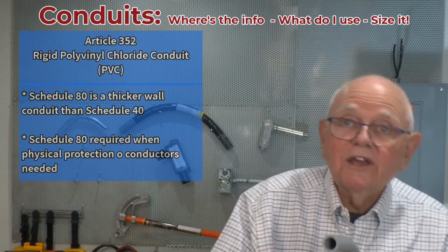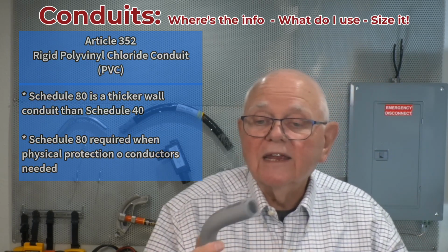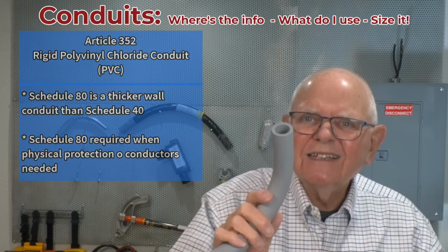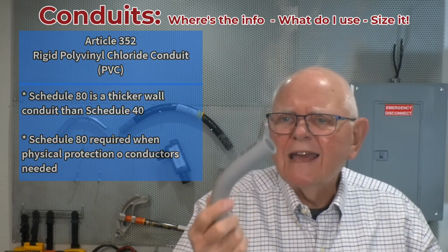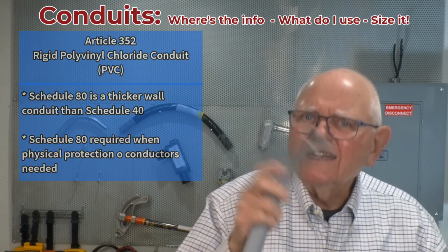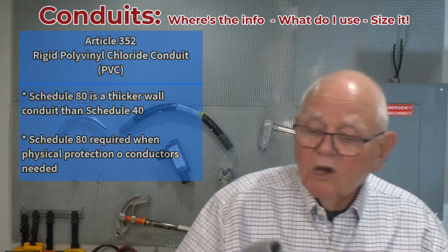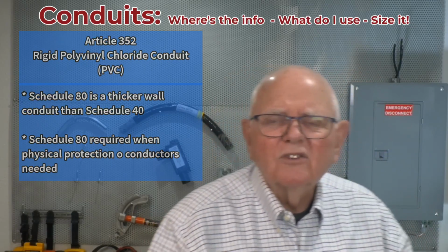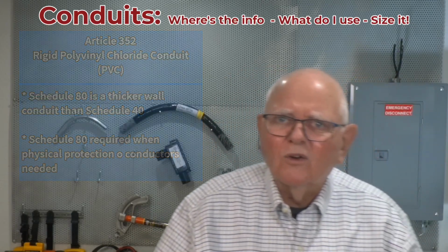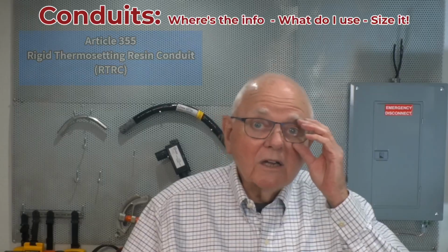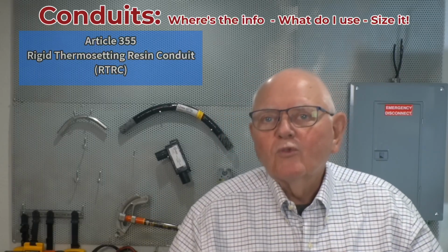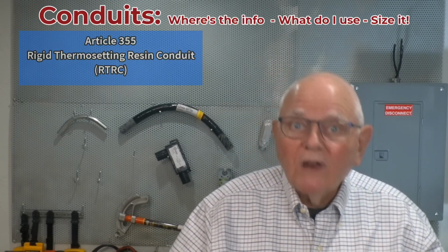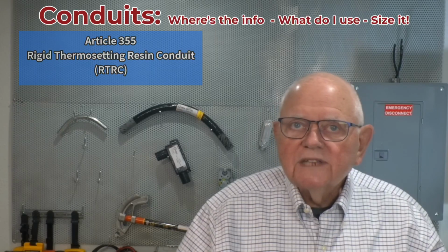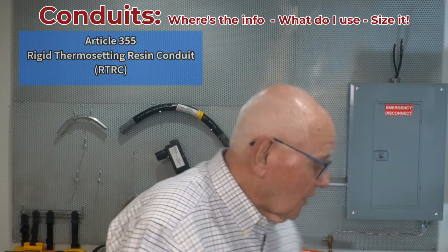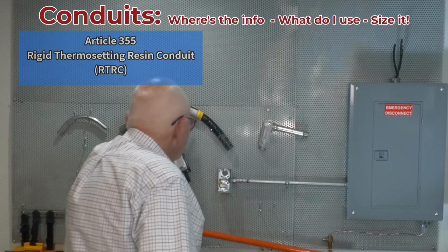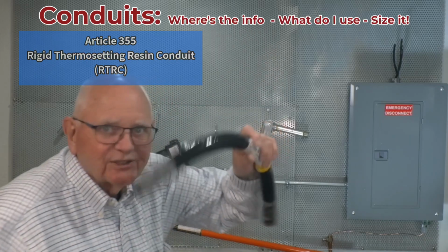So it tells me in the article on PVC conduit, if I'm going to use this to protect conductors from physical damage, I want to use Schedule 80, not Schedule 40. So rigid PVC conduit, we certainly use a lot of that, don't we? Then we have RTRC, reinforced thermosetting resin. Whoa, what is that? Well, you and I have a good name for it. We just call it fiberglass, don't we?